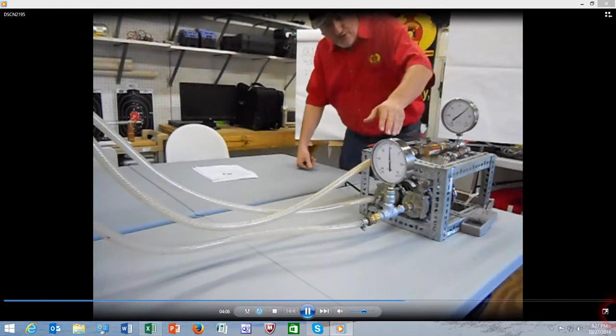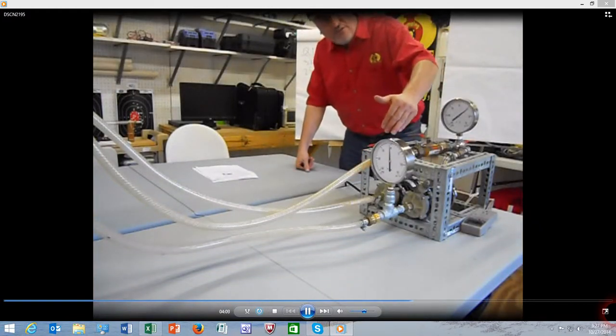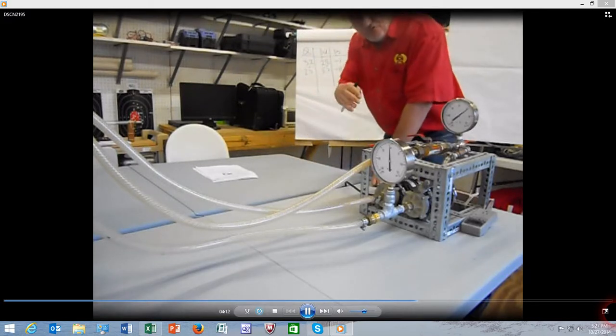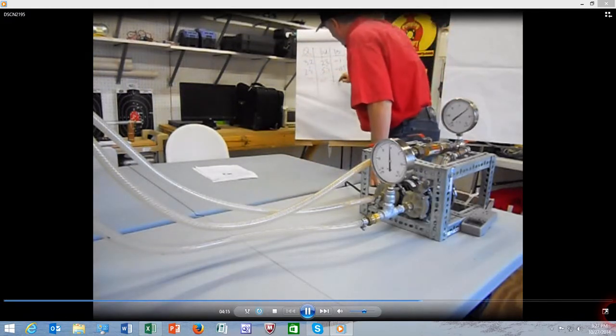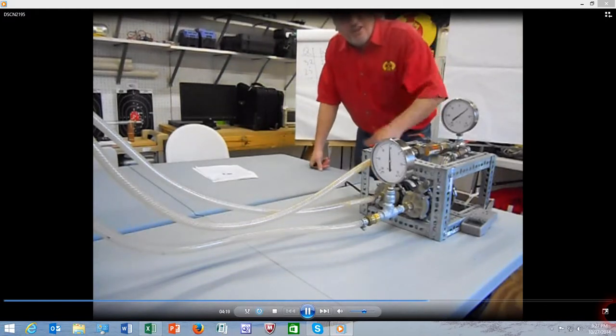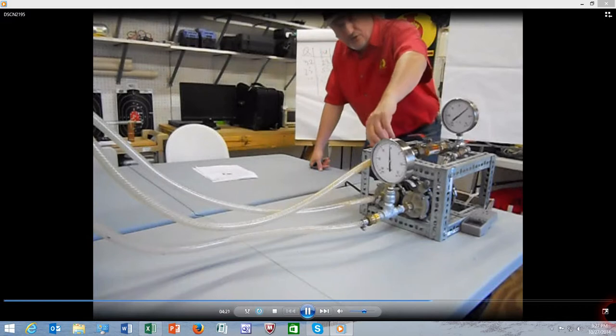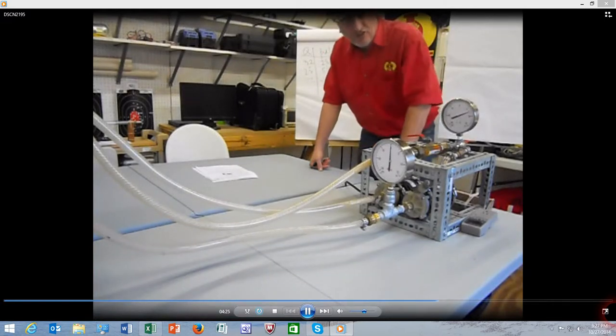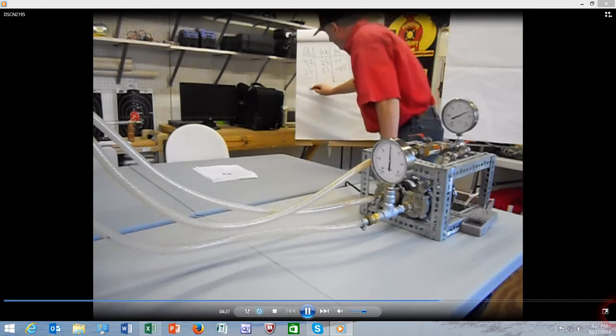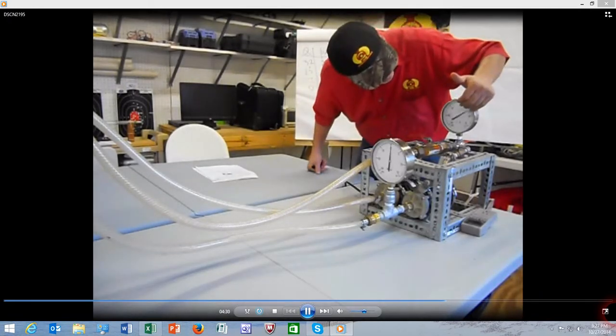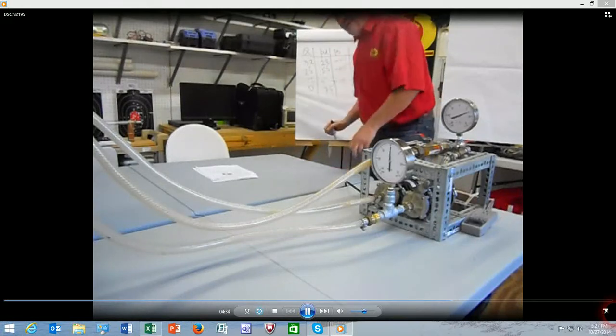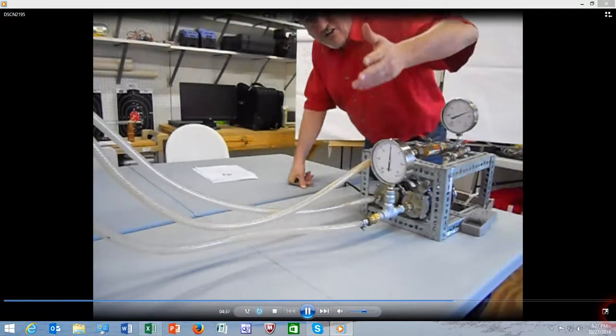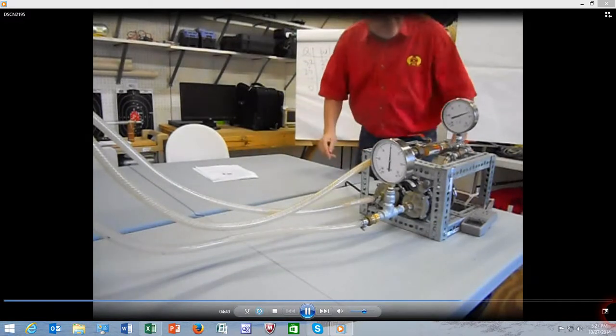And we'll proceed with continuously pinching the valve towards the shut-off condition. I will not do every point for complete test. We'll probably have seven, ten points or so. I'm going to move the valve right to the fully shut condition. The valve is shut. Flow is zero. Discharge pressure is around seven and a half pounds, 7.5 psi. Suction pressure near zero. And the test is complete.